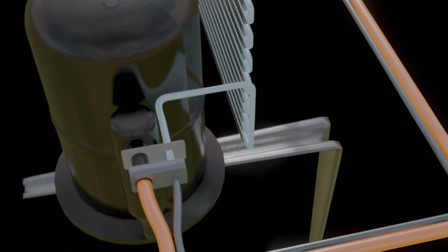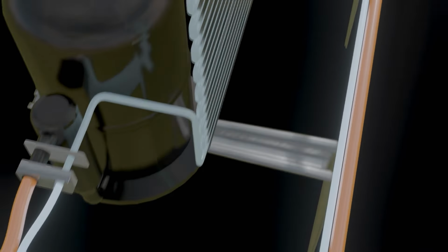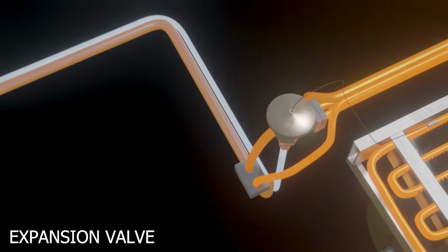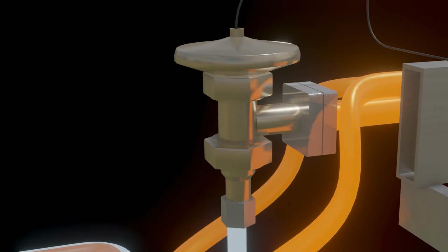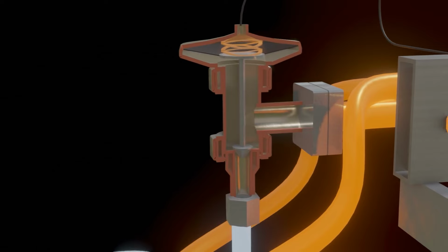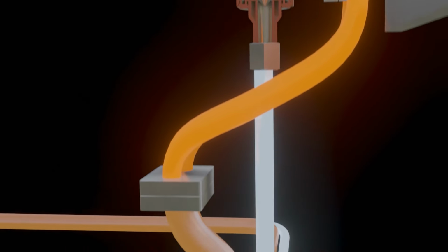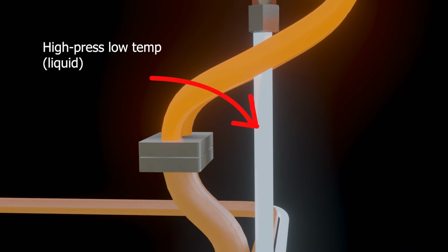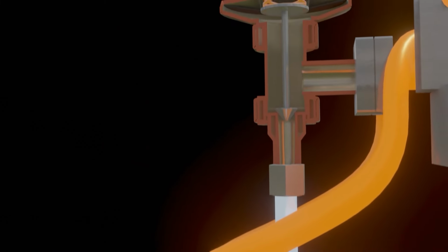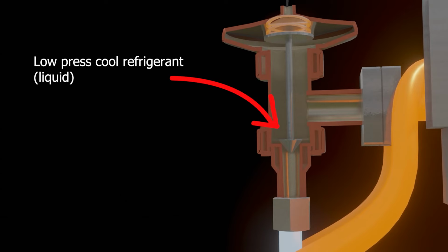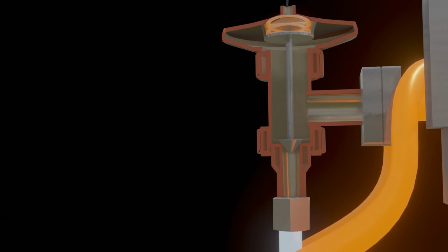After leaving the condenser, the refrigerant flows again to the indoor unit. Here, the refrigerant will enter the expansion valve. The expansion valve is a component that creates a drastic pressure drop effect. This is necessary to reduce the temperature of the refrigerant even colder. In the high pressure position, the heat from the refrigerant has been thrown away by the outdoor unit. But when the pressure is drastically reduced through spraying techniques, the temperature will drop drastically. This is done by passing the refrigerant through a narrow gap. After the refrigerant passes through the expansion valve, it goes directly into the evaporator.